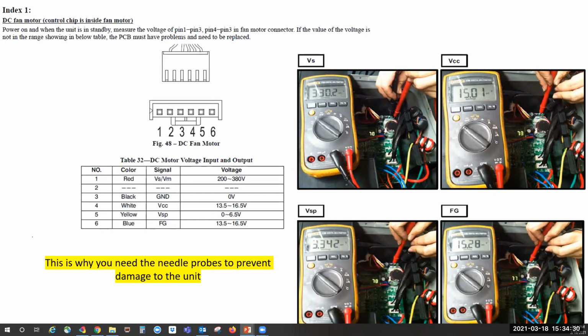With the unit in the standby mode, you should see between pins 3 and 4, 13.5 to 16.5 volts DC. Still in the standby mode, between pins 3 and 5 there should be no voltage because the unit is off. Now you want to check between pins 3 and 6 with the unit off, and you should have between 13.5 and 16.5 volts DC. As long as you have these voltages coming off the board, the board is good, and you need to replace the motor. You can check voltage at the board and at the motor. If you have voltage at the board but not at the motor, then you need to look into your wiring harness. You can check continuity on your wires that way.